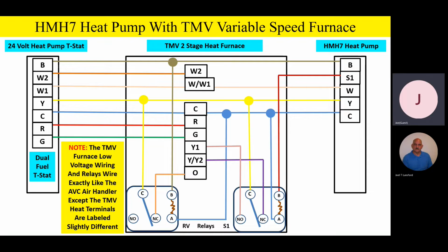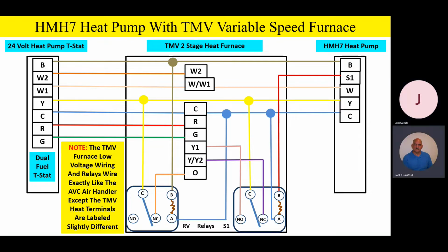So you don't hook up the normally open on that RV relay? That is correct. That's a good observation and question. That normally open is not even going to be used on that RV relay. And as we'll show you in an animation in a minute or two, when we go to heating mode of operation with that B terminal energized for the reversing valve, it's going to switch that relay, and it's going to break that O signal to the indoor board. That's the only reason that RV relay is present, is to break that O signal in the heating mode of operation. That is correct. Good observation.